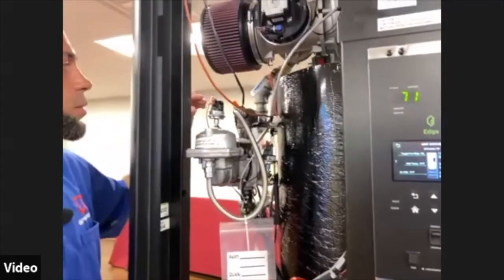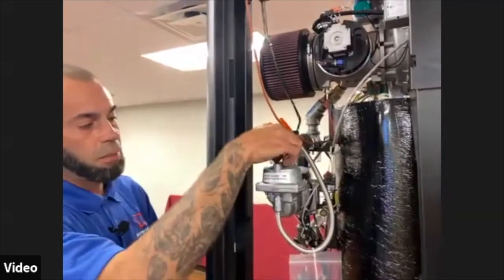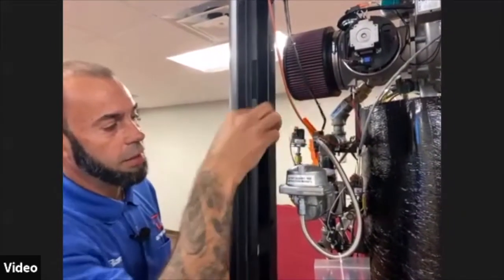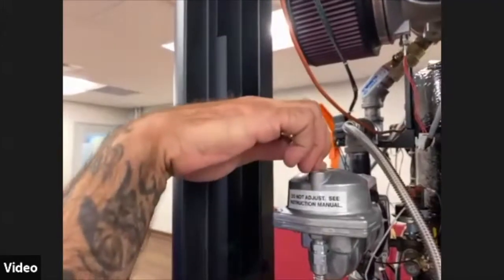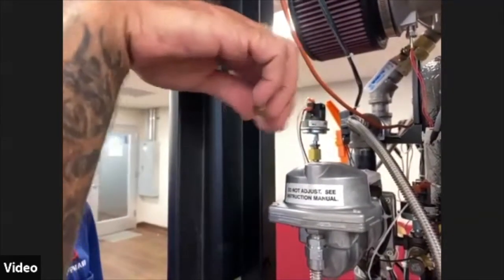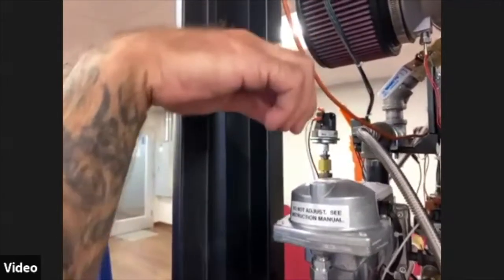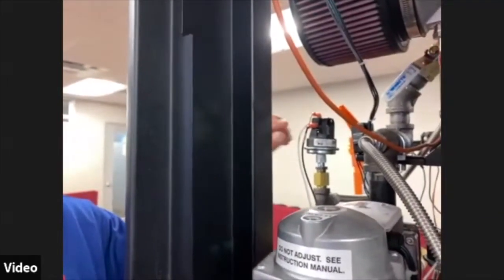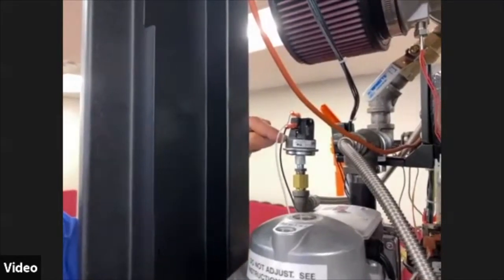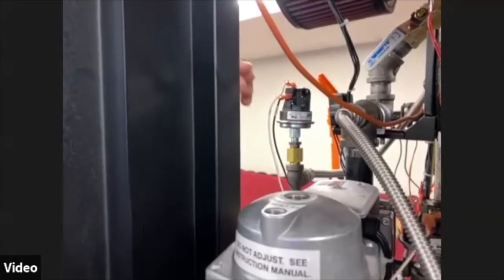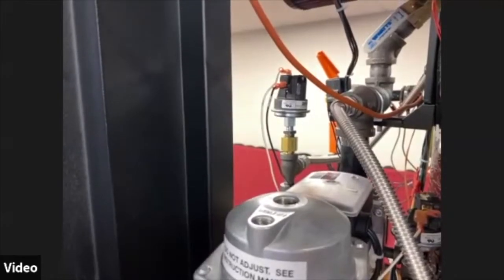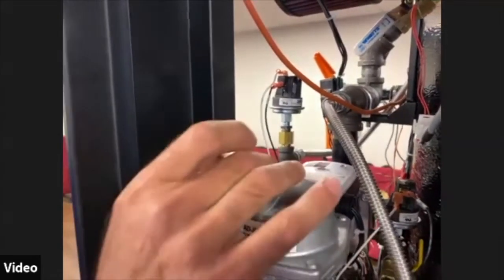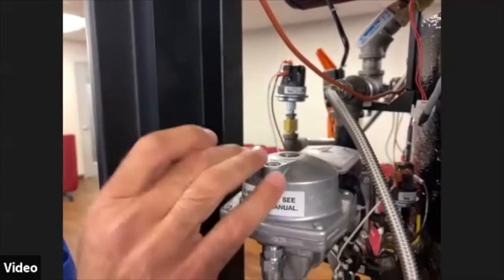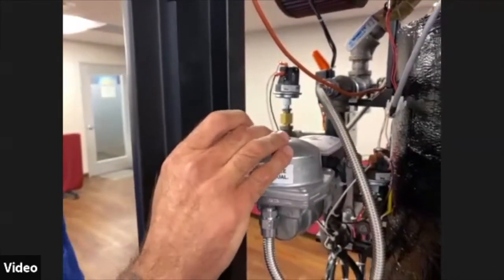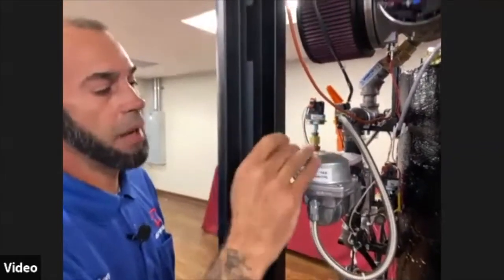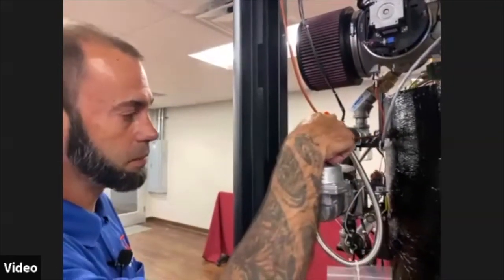Same thing will apply for the high gas pressure switch. The difference is we would take this brass nut out here at the top of the SSOV, and we would start turning the screw in clockwise, increasing the gas pressure until we get above 4.7 inches on our high gas pressure switch. That will allow us to trip the high gas pressure switch, and again, we will go into a gas pressure fault. Obviously, if you do that, verify where your setting is before you make any adjustments here. Bring it back to where it was after you've tested your device.